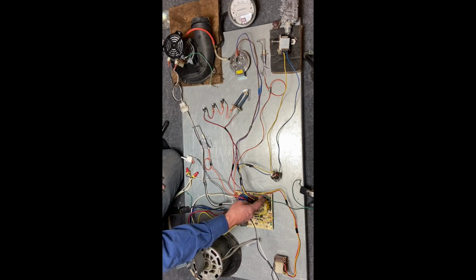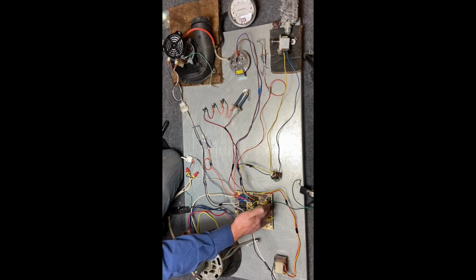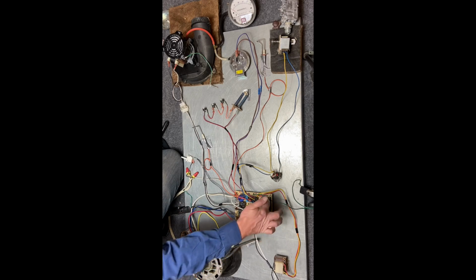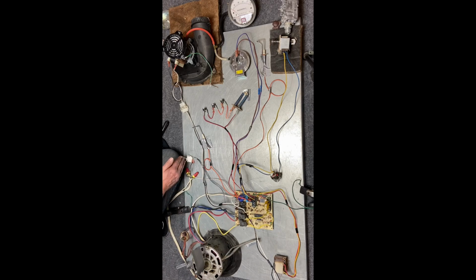Then there, we immediately go into our fuse, and we have our thermostat connections. Now what I've done on the thermostat connections is I've connected from R to W. So when I energize this door switch, we're immediately going to have a call for heating.